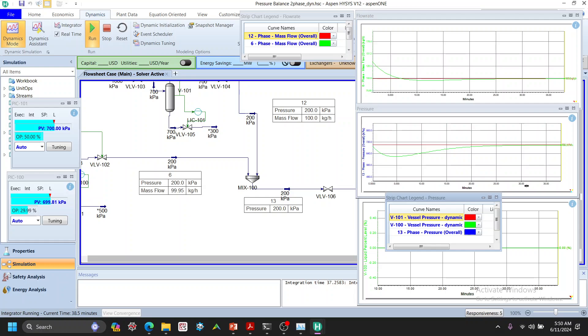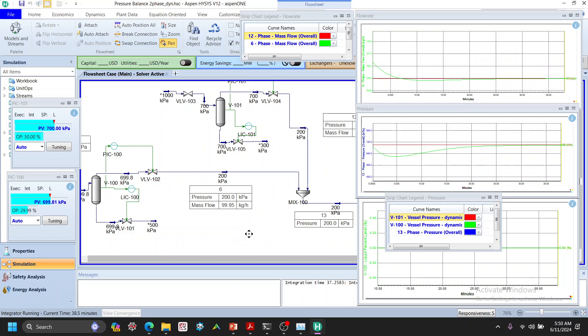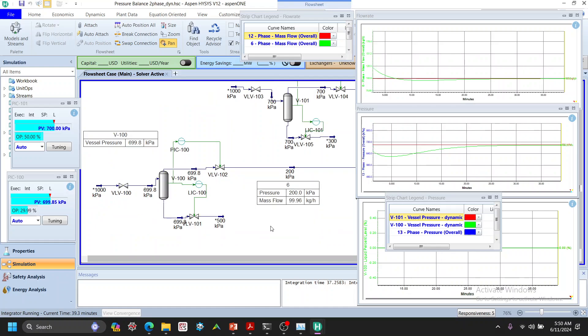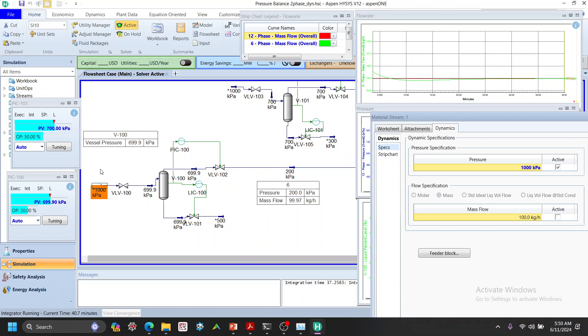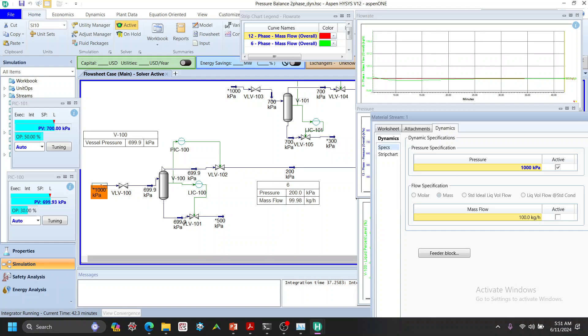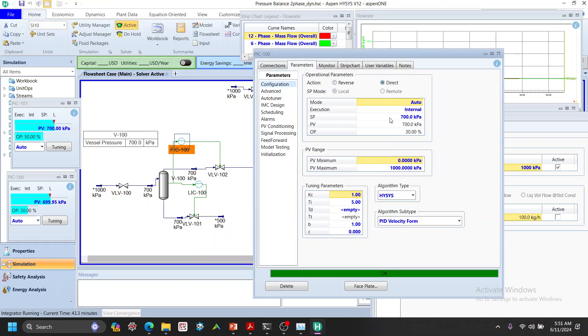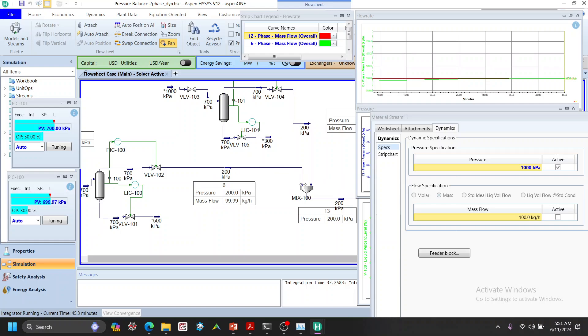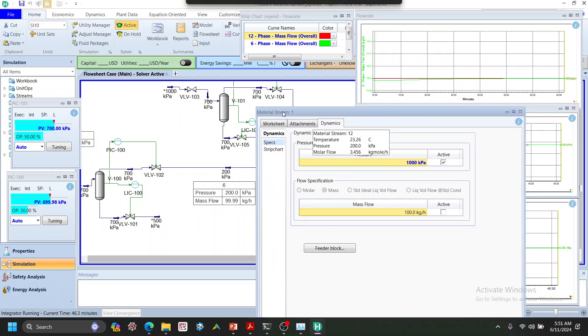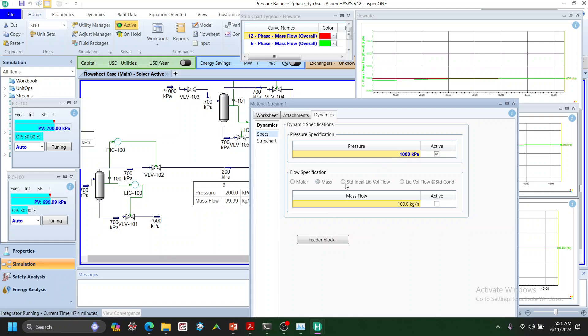It's now at steady state. Now, due to whatever reason, if we increase the source pressure — since we have a set pressure here at 700 kPa — increasing the source pressure with the same 700 kPa set point means more gas will come in, causing pressure in the vessel to increase. The controller will then open the valve more, since it's a direct control valve. So we increase the source from 1000 to 1100 kPa.